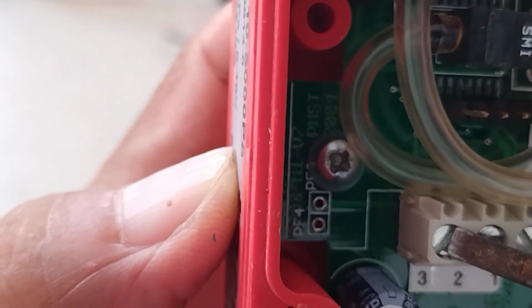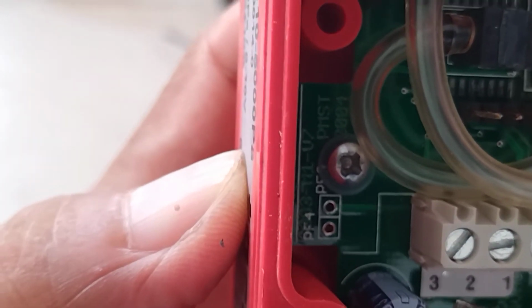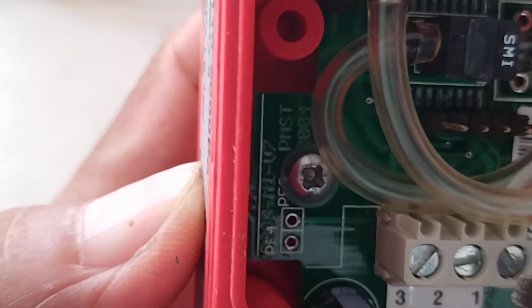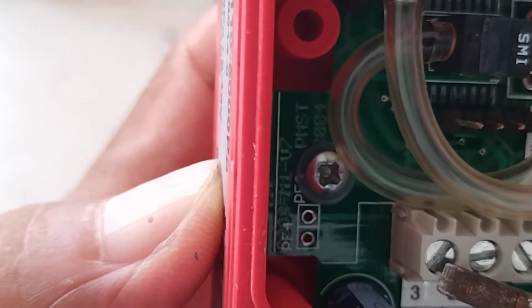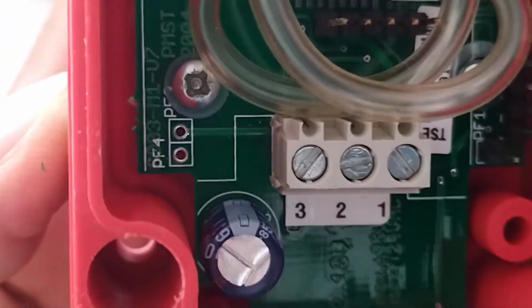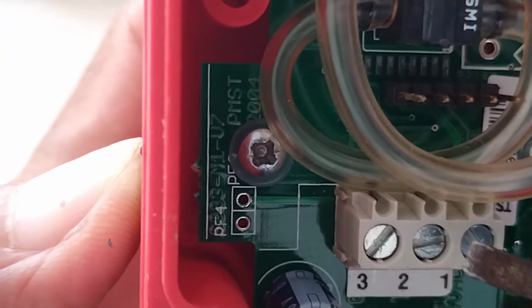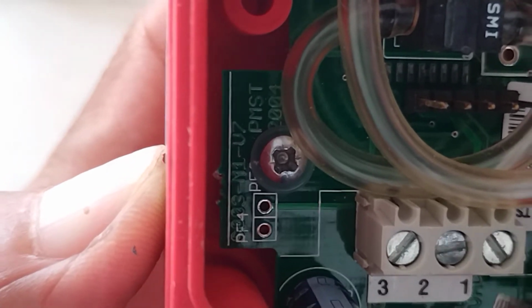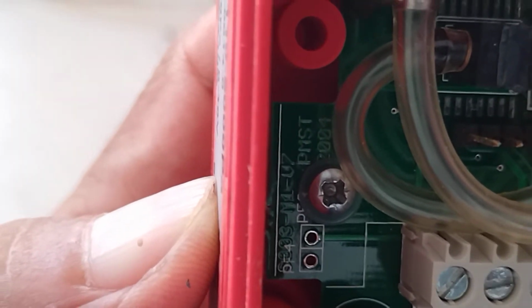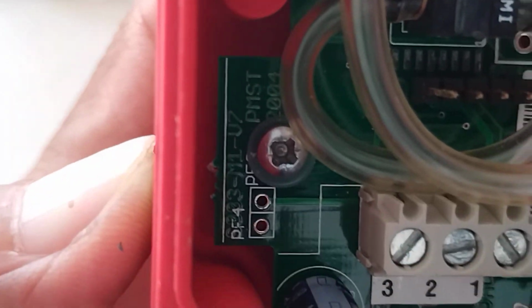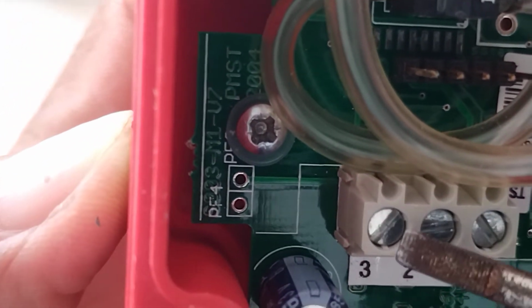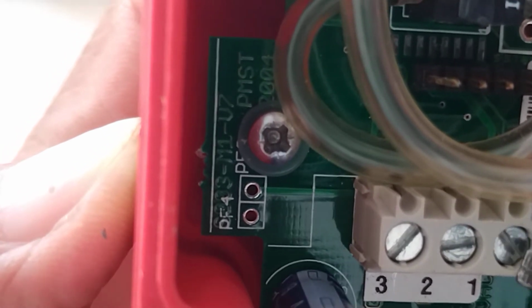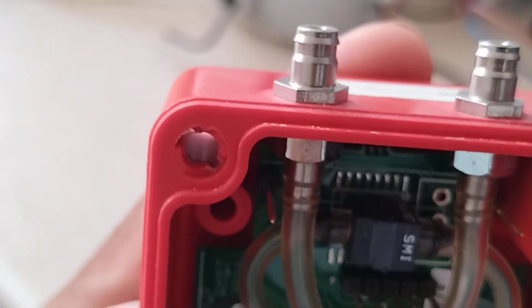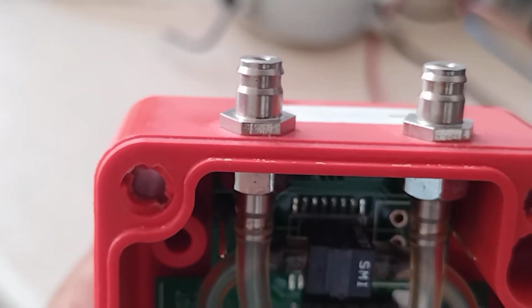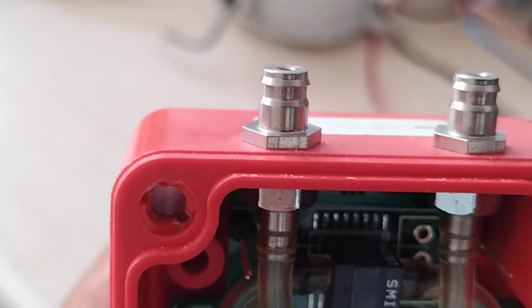So meaning in terminal 3, you will be connecting two black cable or two common cable. One from the power supply and one going to your DDC analog input. So meaning analog input, the symbol there will be signal and ground or common. So you need two core cable here, signal, then common. Then power supply, you need to provide 24 volts, then 0 volts, okay? Then this one will give you the exact differential pressure being sent across a fan, okay?